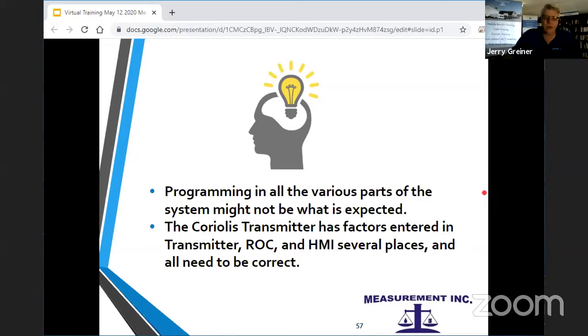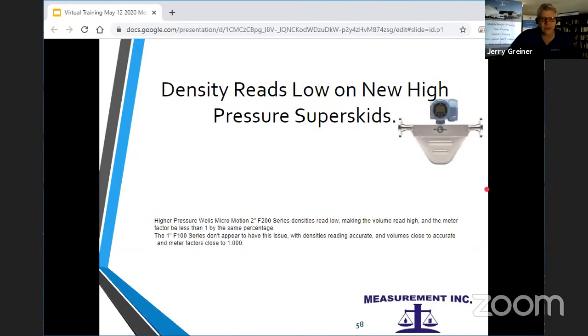Typically, they'll use a pulse input or read over the RS-485 right to the transmitter. This one used a pulse to convert the mass, and then a factor entered for the density. It was a very different way of entering the information, which made it very, very confusing. And that's really why there was an issue here. It was just very difficult to follow.